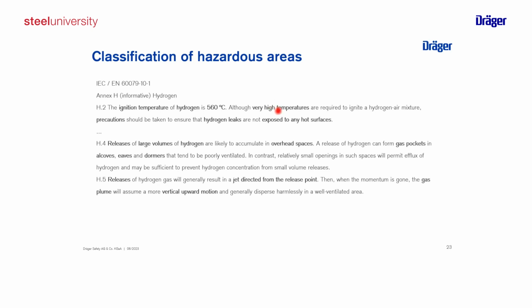But what is different is that hydrogen has a different density, so it is the lightest gas. It will rise up immediately, and if it's in a closed area, you could have an accumulation of your gas in overhead spaces, especially if you have a closed roof and areas which are not very well ventilated. The gas will collect there, and it will stay there because there's no air exchange.